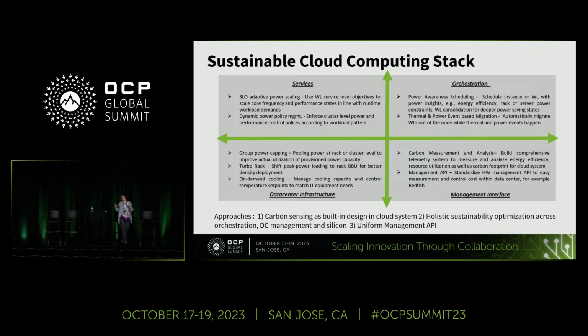There are two mechanisms that we have built in. One is the hardware part of it. So if it starts peaking, the battery backups can take that extra power. Or if you don't want that, the software layer control kicks in, where you start capping some of the workloads which are least critical, and still maintain within the power budget.